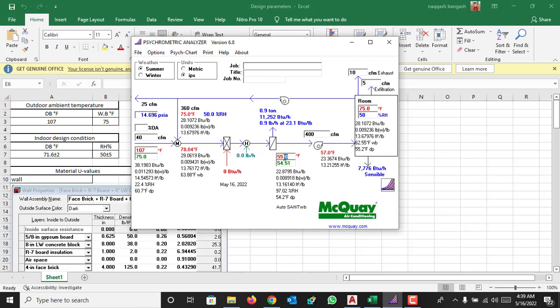And supplying air at 55 Fahrenheit which is 400 CFM, and the total return is 360 while adding 40 CFM as fresh air. So the total supply air is 400, in this case it's 0.9 ton of refrigeration required to cool down that much air.